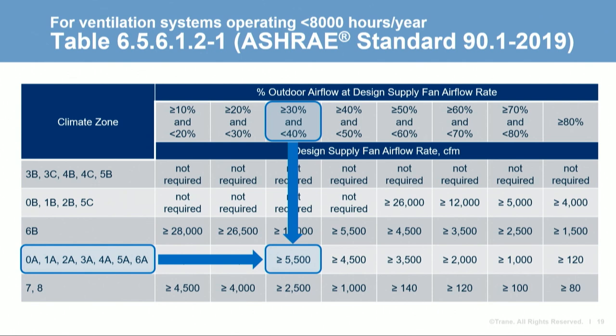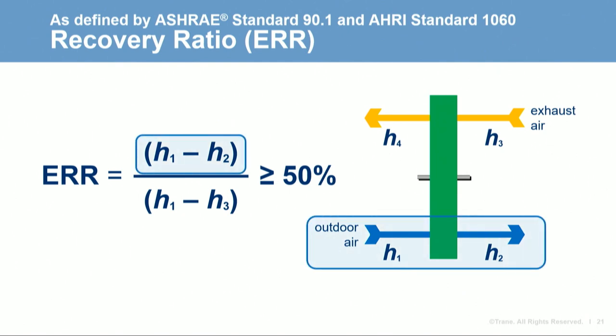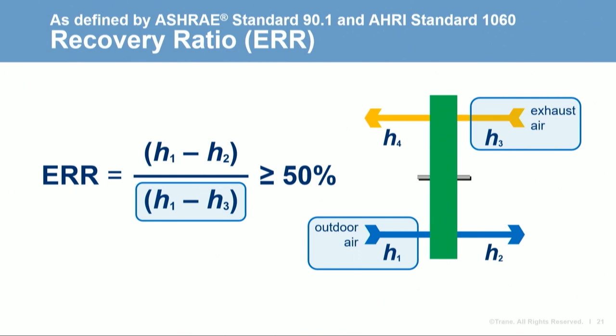When it is required, the energy recovery system must result in an enthalpy recovery ratio of at least 50%, required at both heating and cooling design conditions. The ratio is defined as the change in enthalpy of the outdoor air as it passes through the supply side of the device from H1 to H2, divided by the difference between the enthalpies of the entering outdoor air H1 and the entering exhaust air H3. The standard requires this minimum performance at both conditions unless one of the exceptions applies.